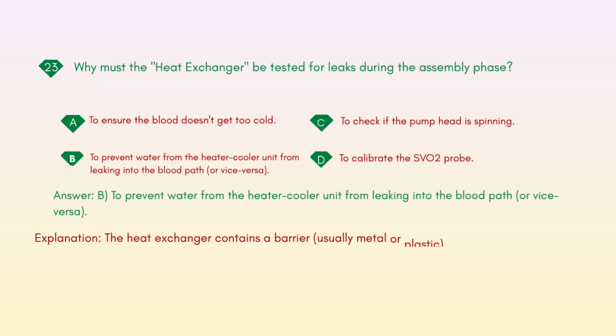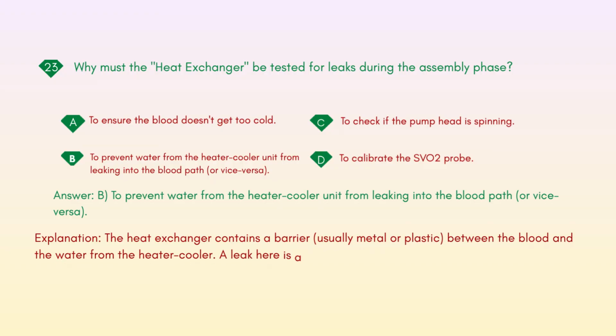Explanation: the heat exchanger contains a barrier, usually metal or plastic, between the blood and the water from the heater-cooler. A leak here is a catastrophic failure that can lead to hemolysis, water intoxication, or sepsis.